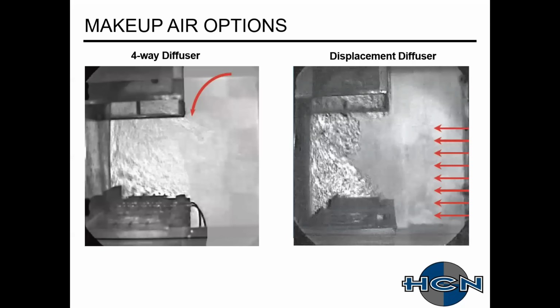So just some quick Schlieren pictures of what they did in the testing labs. With the 4-way, you can see here they're typically high throw discharge. What happens with that is when it hits that front face, it goes down, kind of creates a curtain, which is that cooler air pulling that exhaust and effluent out of the hood, so then you're getting capture failures. Displacement diffusers, like we discussed, have nice laminar linear flow, push that exhaust back in there, it gets circled in, and does what it's supposed to do.